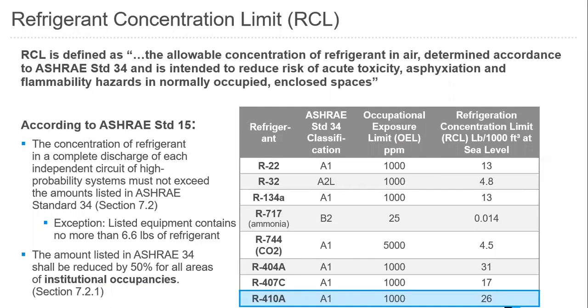So you can see that within ASHRAE 15, there's a table. It looks like the table I'm showing here on the screen. And here on this table, I'm showing just some key refrigerant types. So we've got R22, R410A, and you can see called out here within this table, we have ASHRAE standard 34 classifications. We have an occupational exposure limit, or an OEL, which is in parts per million. And then we also have a refrigerant concentration limit, which defines the maximum pounds per 1,000 cubic feet that we can have within a space at sea level. So R410A, for example, has an ASHRAE standard 34 classification, which I mentioned in the previous slide, of A1, an occupational exposure limit of 1,000, and a refrigerant concentration limit of 26 pounds per 1,000 cubic feet at sea level.